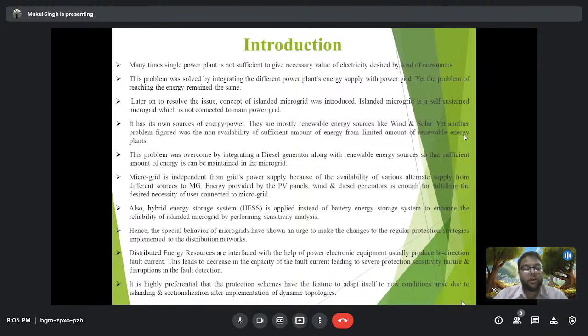The special behavior of microgrids has shown the need to make changes to the regular protection strategies implemented in the distribution network. Distributed energy resources are interfaced with the help of power electronic equipment, which usually produces reduced fault current, leading to a decrease in fault current capacity.